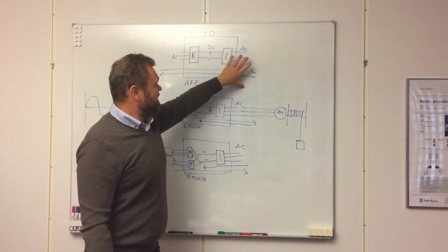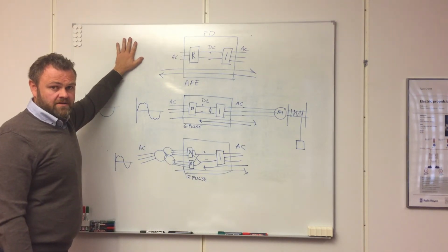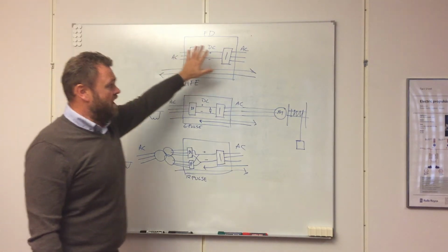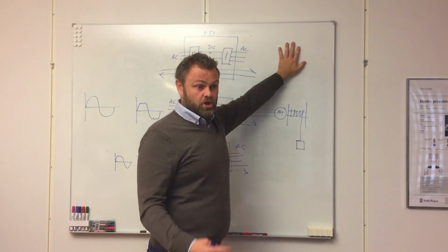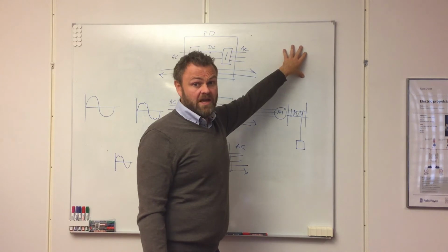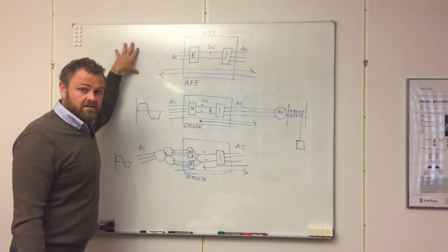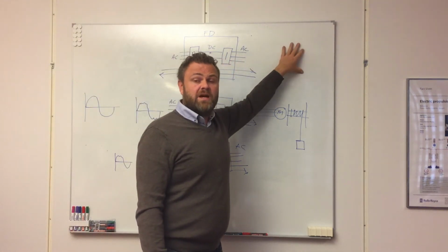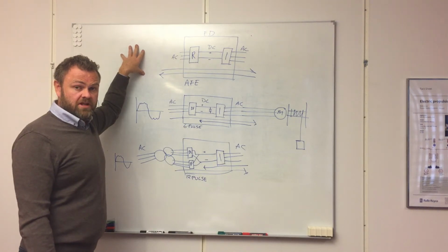And we can brake that energy by the load on the grid. So if you have a hotel load over here, you can brake whatever over here. Well, you may say, can we brake really a huge propeller, 5 megawatt? Can we brake that propeller by load on the grid? Yes, we can. We can brake a 5 megawatt propeller by just a small load on the grid.